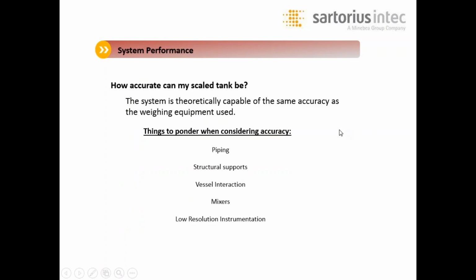How accurately can my scaled tank be? The system is theoretically capable of the same accuracy as the weighing equipment that's installed. If you have a 0.5% load cell, you should have a system that's 0.5% in a perfect world. Unfortunately, we have issues when it comes to tank and vessel systems that cause some ambiguity in what that final number can be: the type of piping that the customer is using, structural supports, other vessel interactions, a mixer or any kind of motor that's mounted to the vessel itself, and low resolution instrumentation. Are they using a high resolution process controller?